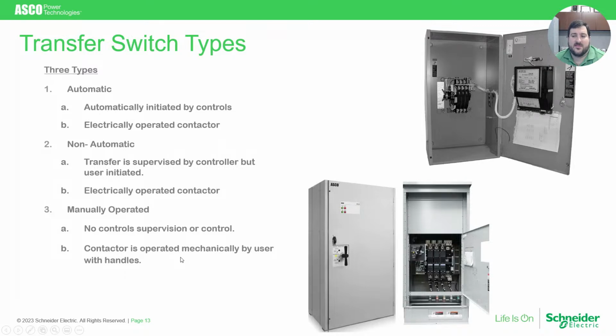So again, the main difference is an automatic switch has a controller that will function automatically. A non-automatic still has a controller, but a user has to press a button or send a signal to the switch to initiate the transfer. But a manual switch has a physical handle that somebody must physically turn on it to transfer to emergency power.